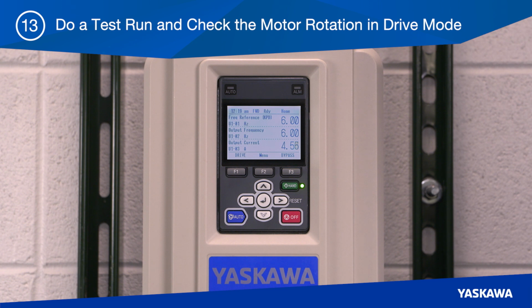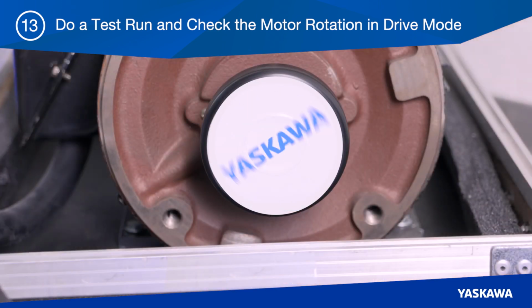Review the output current U103 and make sure that the displayed value is appropriate for the load and current rating of the bypass and motor used in this application. Now, observe the motor rotation for proper direction.